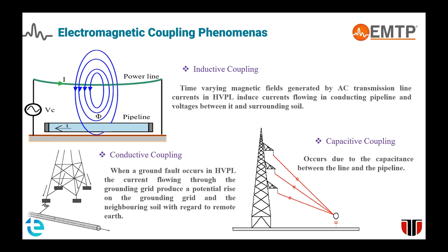In the following, I will discuss how we can model these phenomena in order to evaluate the induced voltage, using a case study between an ideal 400 kV power line and a gas distribution metallic pipeline, placed underground at 1.2 meters depth, at a separation distance of 50 meters from the high voltage power line.